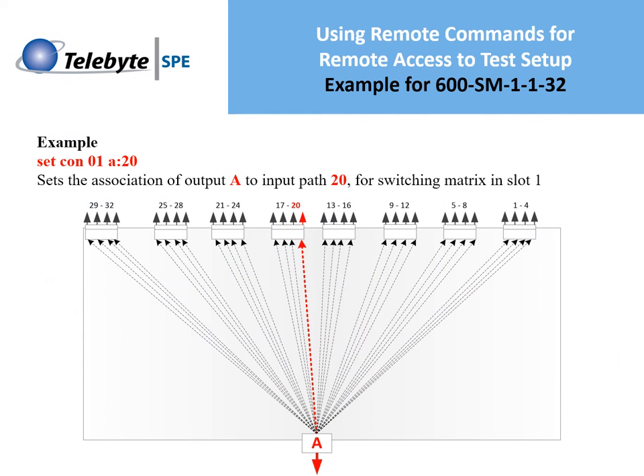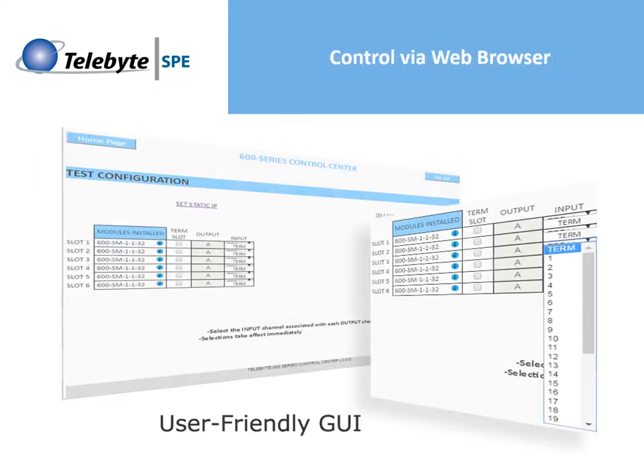Here's an example of a command that can be used to control the 600SM 1x1x32 switch. The command is setting the association of output A to input path 20 for the switching matrix module located in slot 1 of the chassis. The 600 switching modules can also be controlled via a web browser.